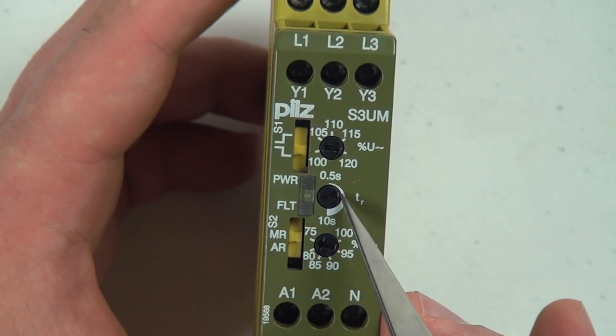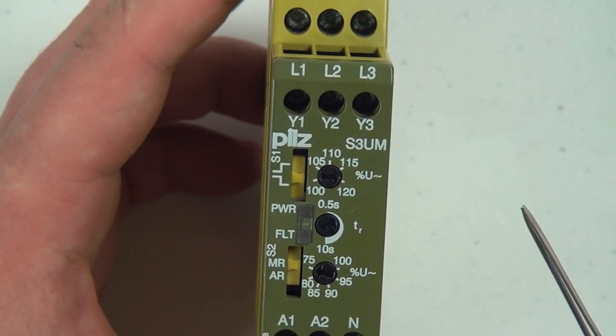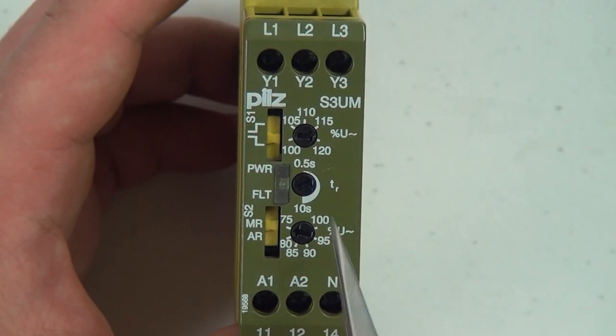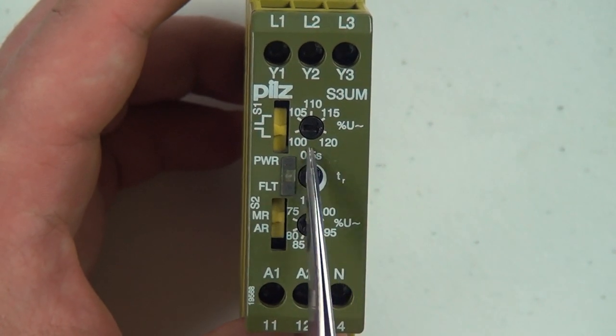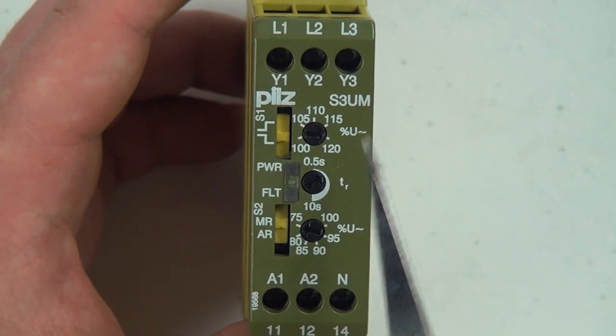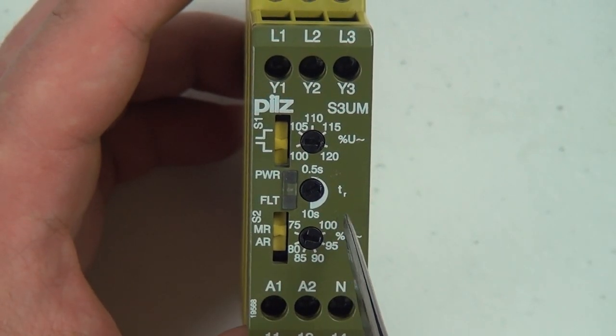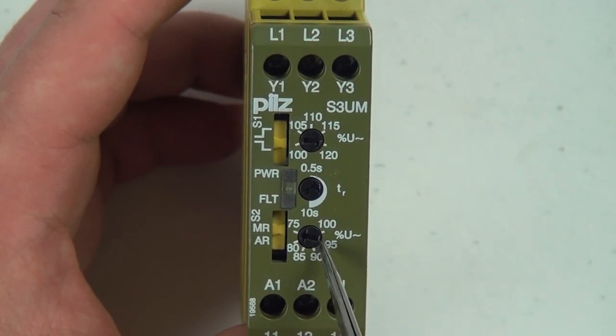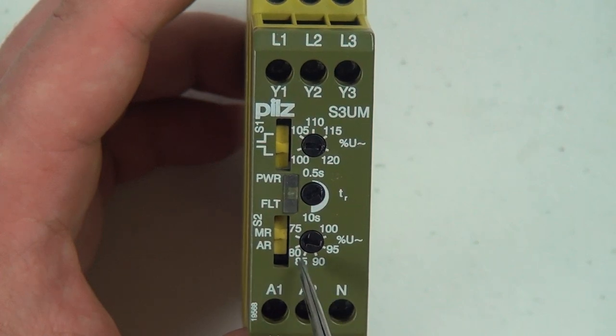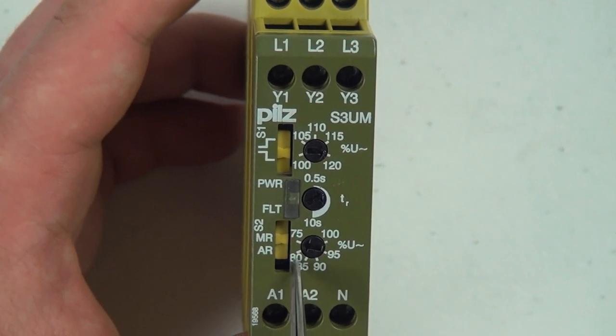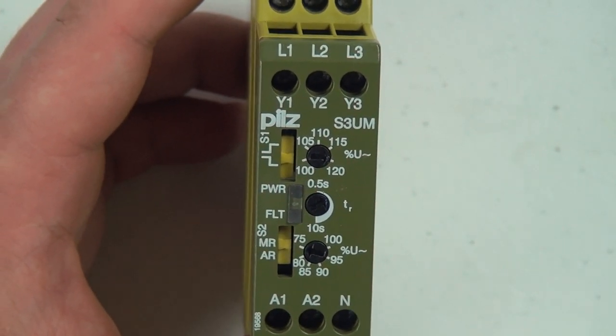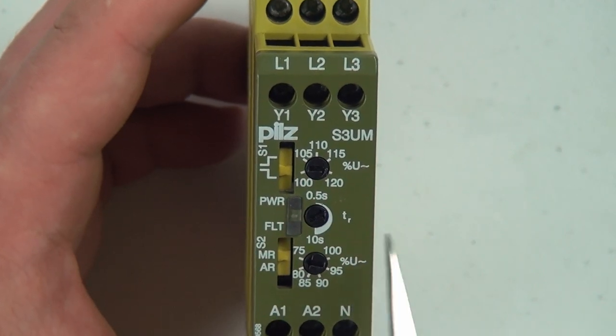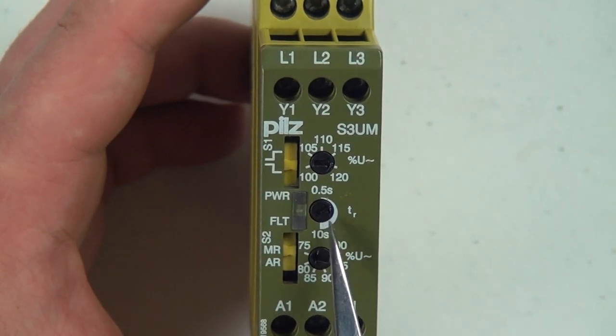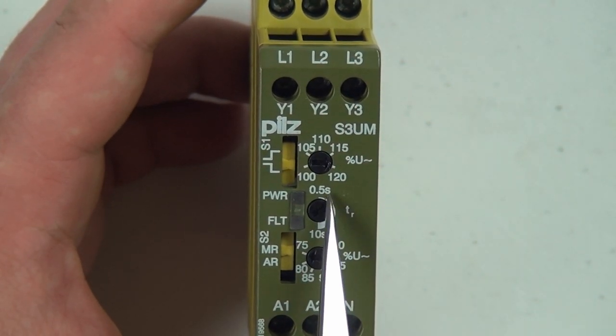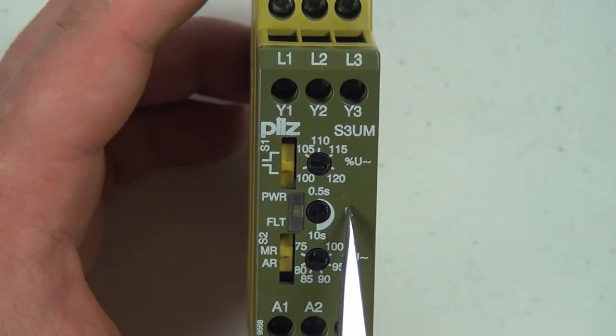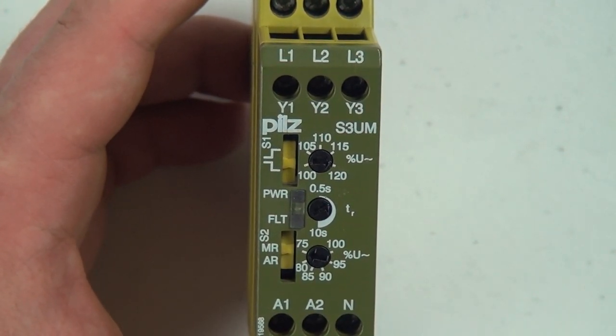The reason for this time delay feature is that, let's say you have a large industrial motor that's starting up, and that motor can draw some extra juice. And while that motor is starting up, which for a motor tends to be its peak consumption, the voltage can droop a little bit. And so if we set our undervoltage to 90, but our voltage will actually droop to below 80% of the set voltage, you can say that, okay, I want to set my time to 5 seconds because the motor would have already spun up by that point in time. And so I can avoid the trip by delaying my trip to 5 seconds because my voltage levels would already have come up by that point in time.